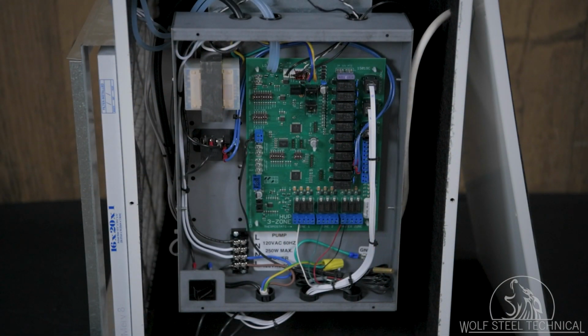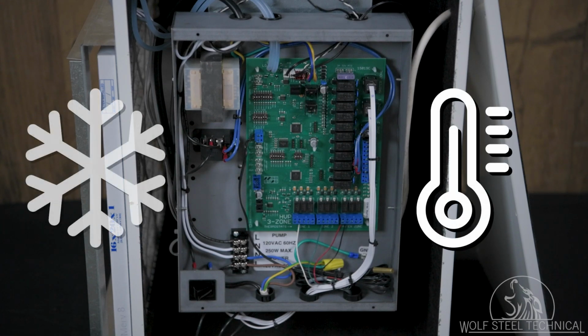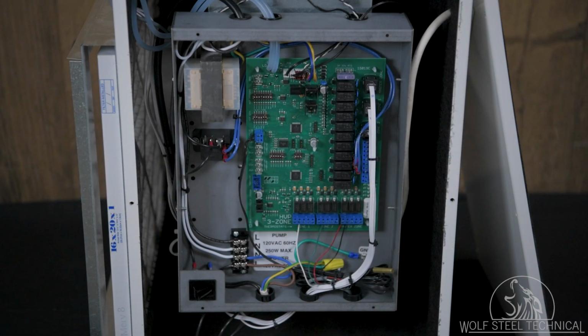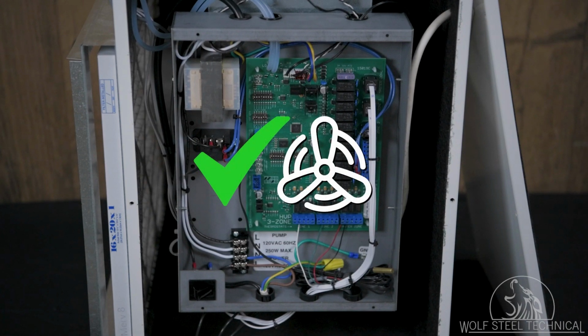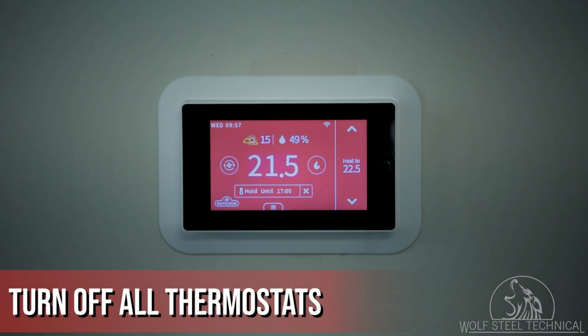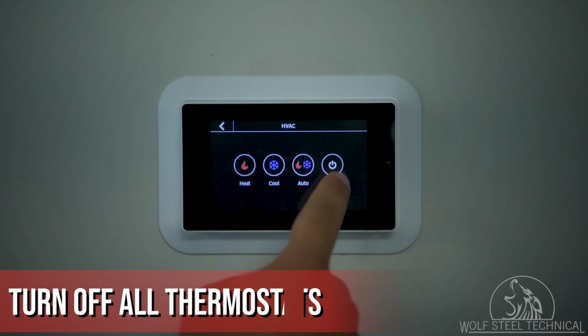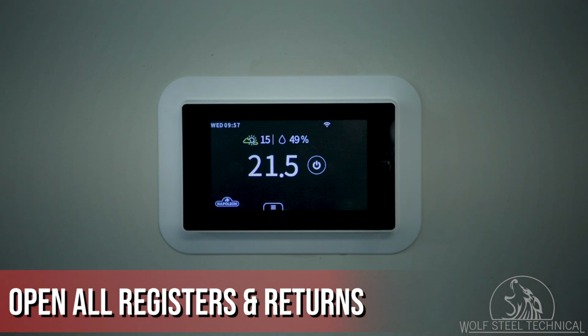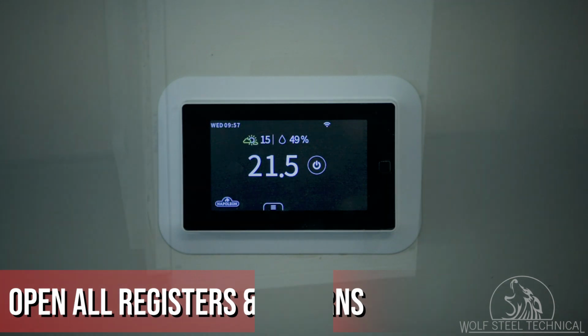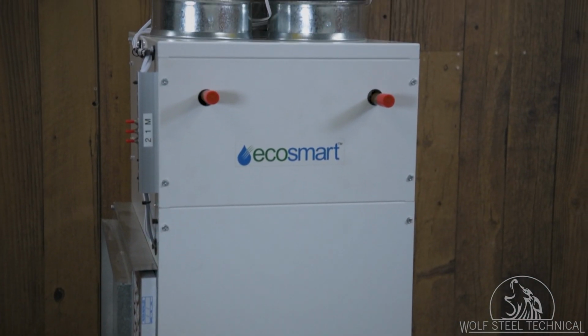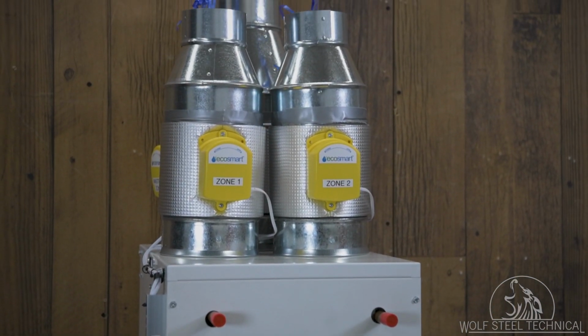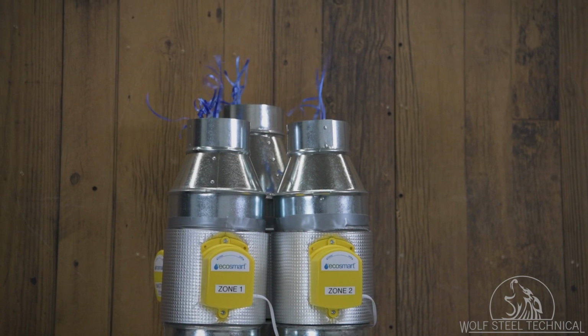Two values of CPT are stored in the system, one for heating and one for cooling. It's recommended to calibrate both the heating and cooling at the time of installation. This allows for correct fan operation under CPT. To begin, locate all the thermostats in the home and set them to the off position. While doing this, ensure all supply and return registers are open in the home. It's important to note that the EcoSmart can be calibrated even if the thermostats have not yet been installed.